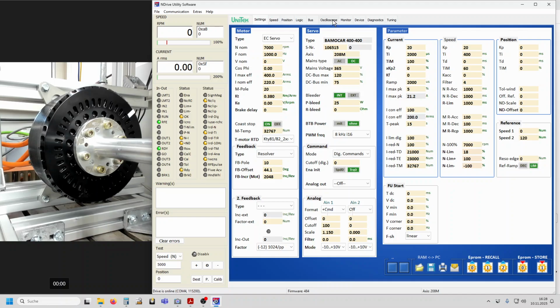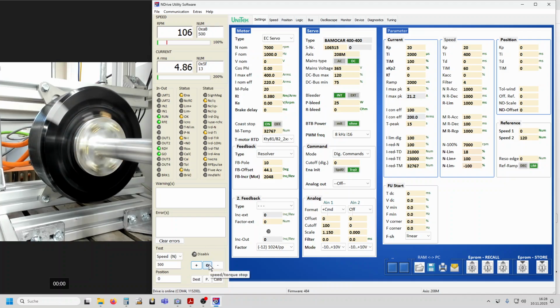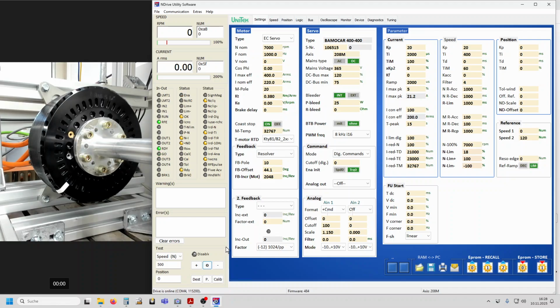For this demonstration, it is very helpful to have everything already configured correctly, meaning you can actually control the motor as desired. So the motor pole number is correct, the general configuration is correct, the motor pole feedback is configured correctly, and you can actually, as I'm going to demonstrate to you now, control the motor as desired by sending speed or torque requests. It is also recommended that you have a free running motor, and that you limit the current output for safety purposes.